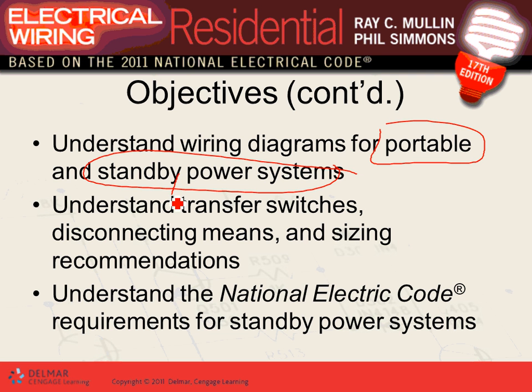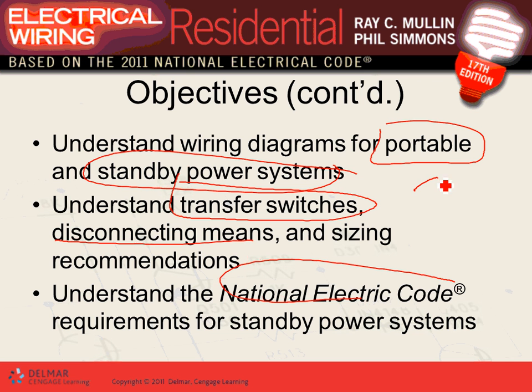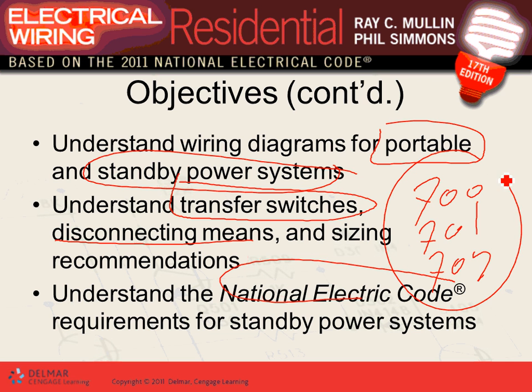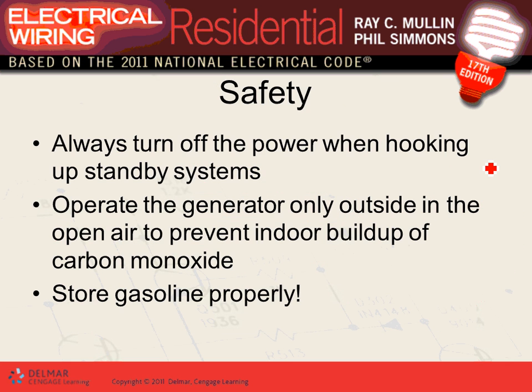With standby and generators, there's a term called a transfer switch. Disconnect means and size recommendation. Generator installations require you to have a disconnect, a wire that goes from the generator to your power system, and a means of transferring the power from the generator to the utility and vice versa. They call this a transfer switch. You're going to see it in a second. Recommendation for standby power system: like I said, there are three articles, 700, 701, and 702. We will talk about this not today but as we move into the commercial, because it applies more to the commercial.